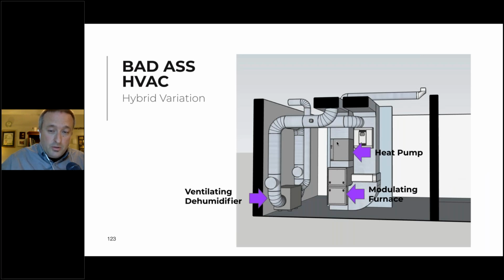So here's a nice furnace and a modulating heat pump on top. But if you're going to have good dehumidification control, you can't do reheat - you can't pump heat into a coil when you're trying to cool it. You have to do a separate dehumidifier, and again, that's an expensive rig.